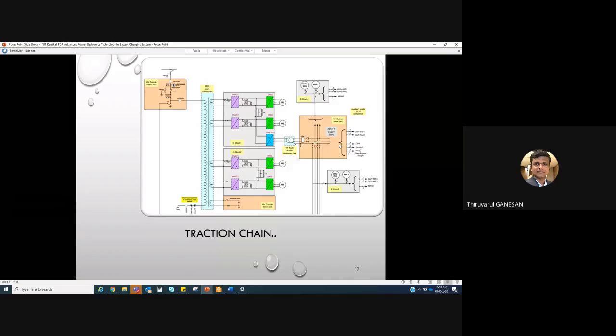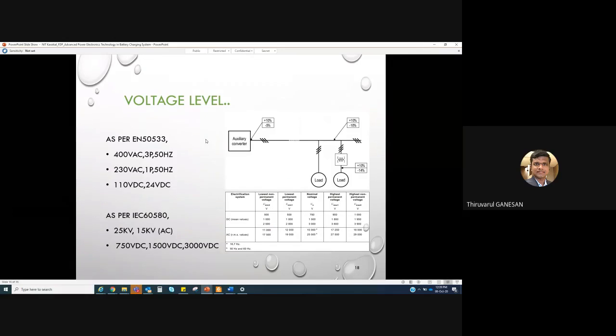So this is the EN and IEC standard for a voltage system. What are the tolerances we can allow for individual voltage levels? For example, as per EN 50533, for all auxiliary loads on a 400 volt three-phase system, you can go up to 10% on the positive side and minus 5% on the negative side. Also for 230 volt and 110 volt systems.